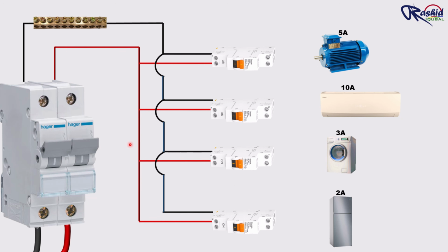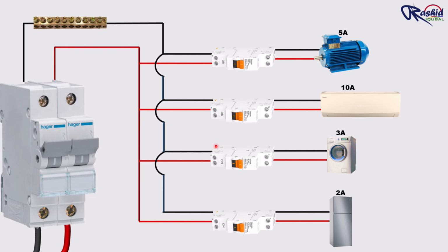For example, if we redesign this panel and install a separate RCBO for each load circuit, every circuit gets individual protection. Suppose a leakage fault occurs in the refrigerator circuit, only the refrigerator RCBO will trip, while the motor, AC and washing machine circuits will continue operating.